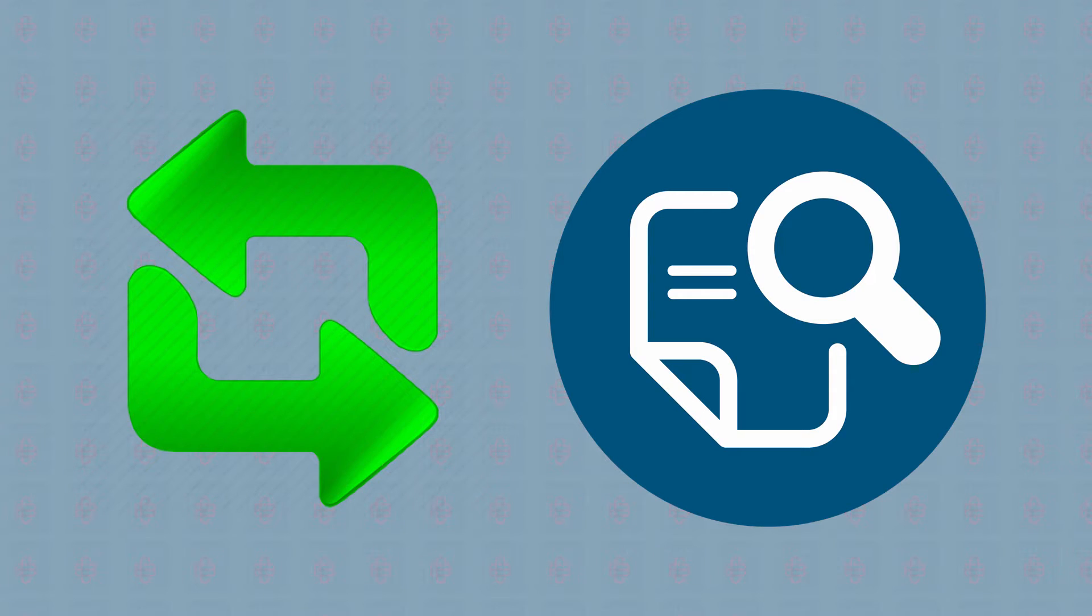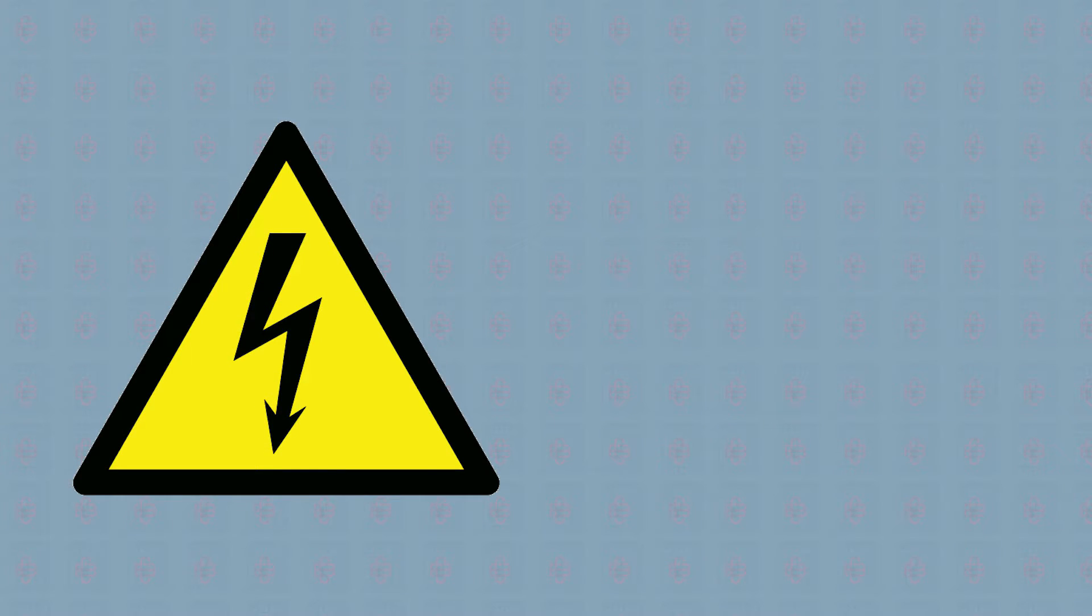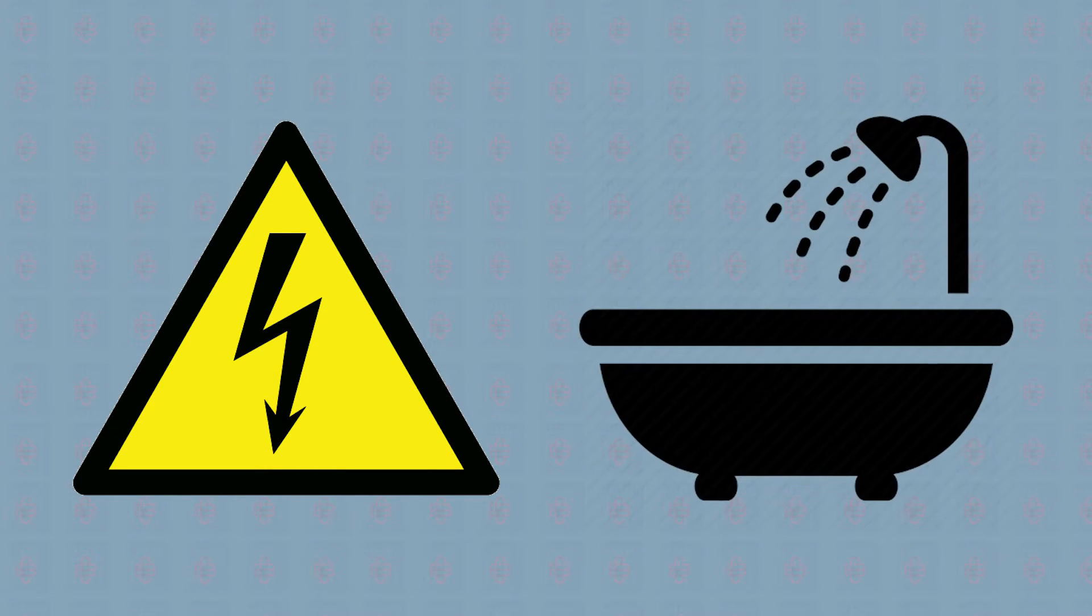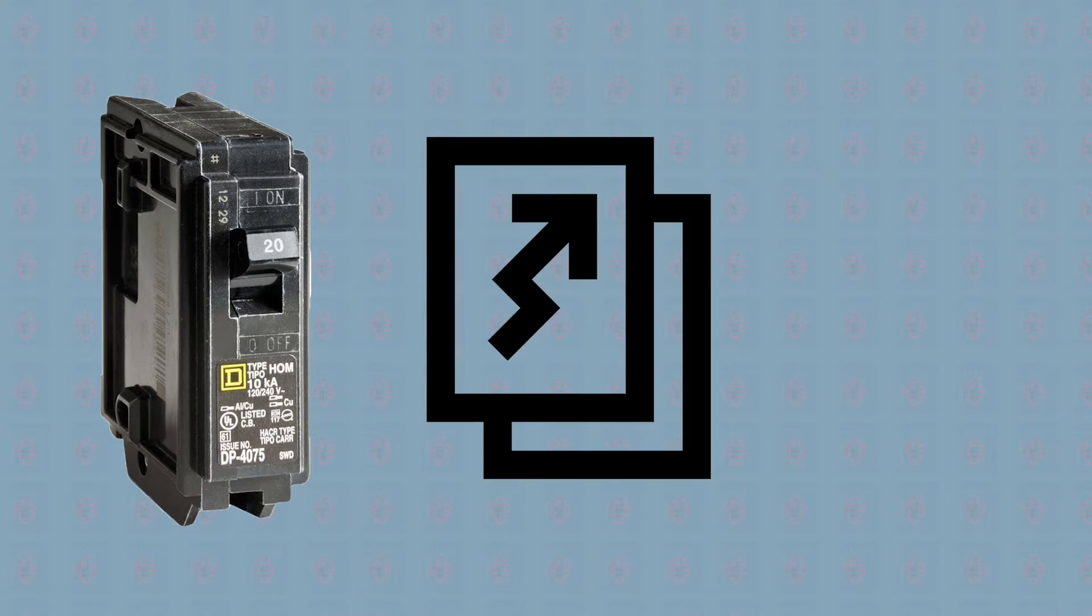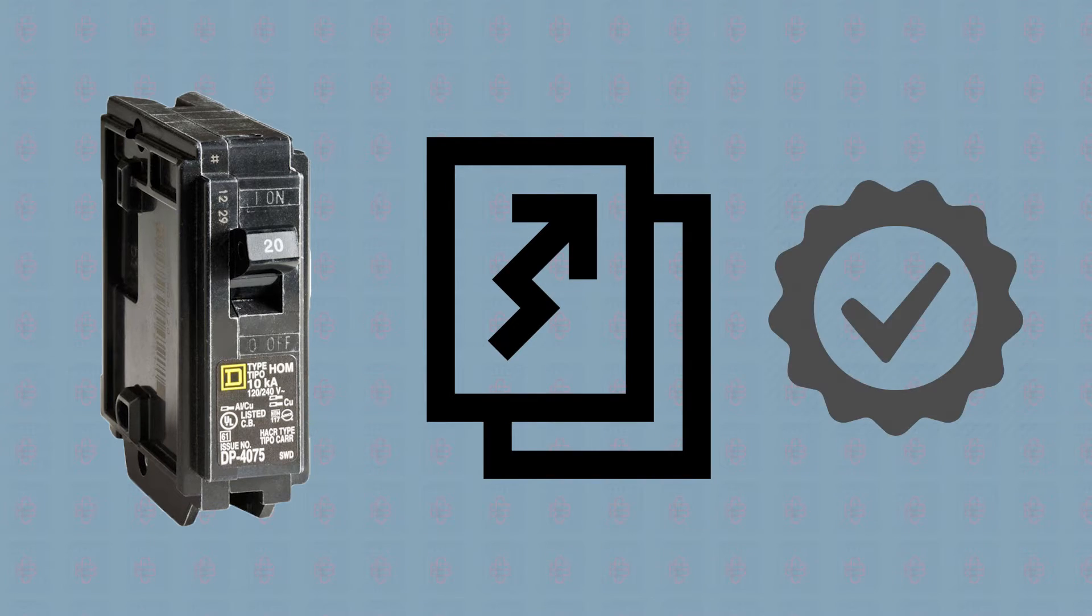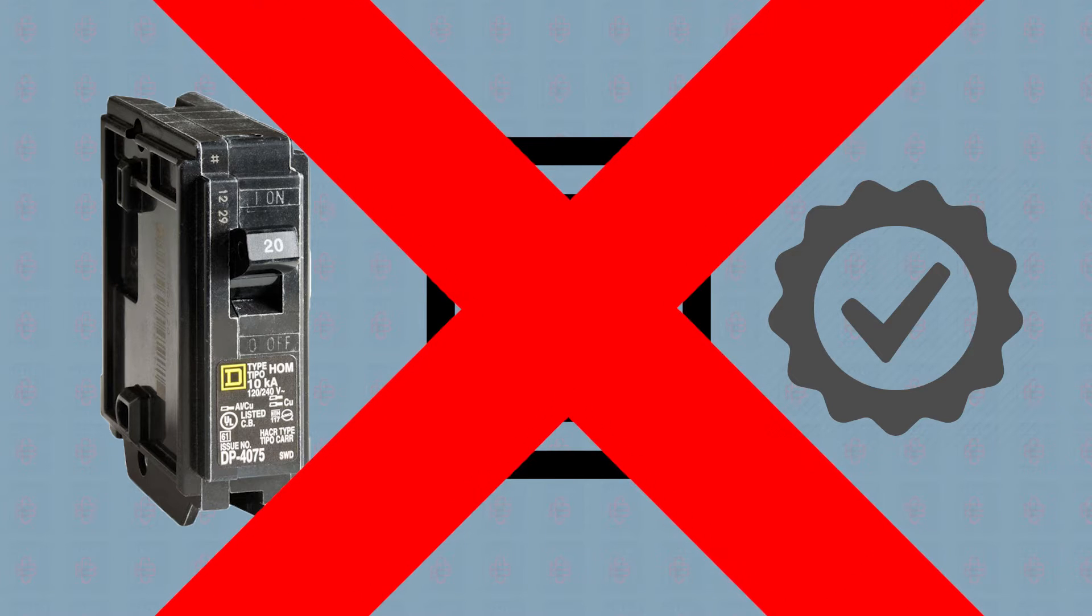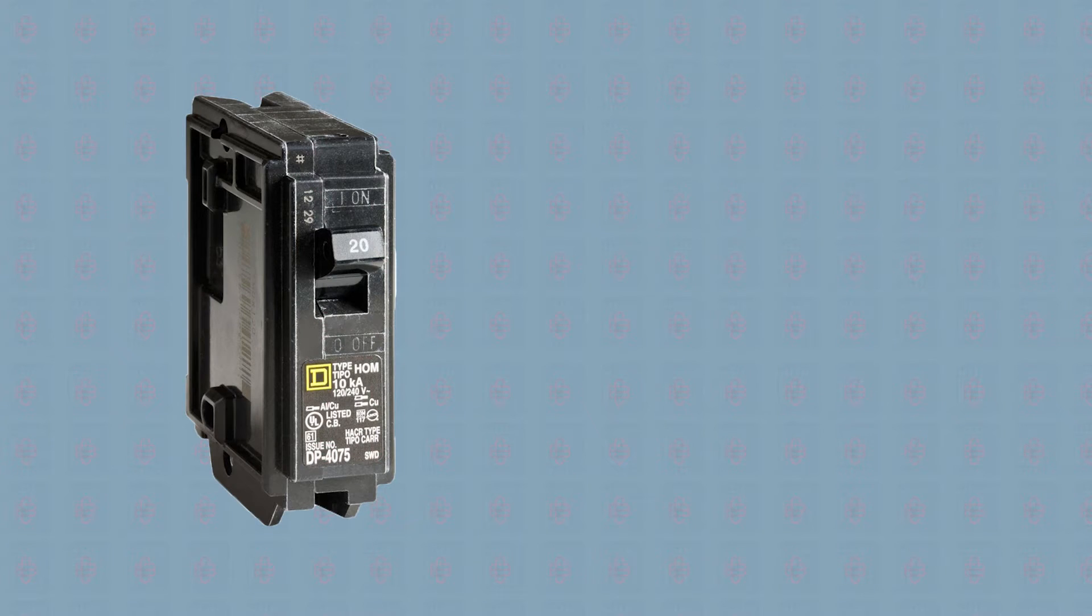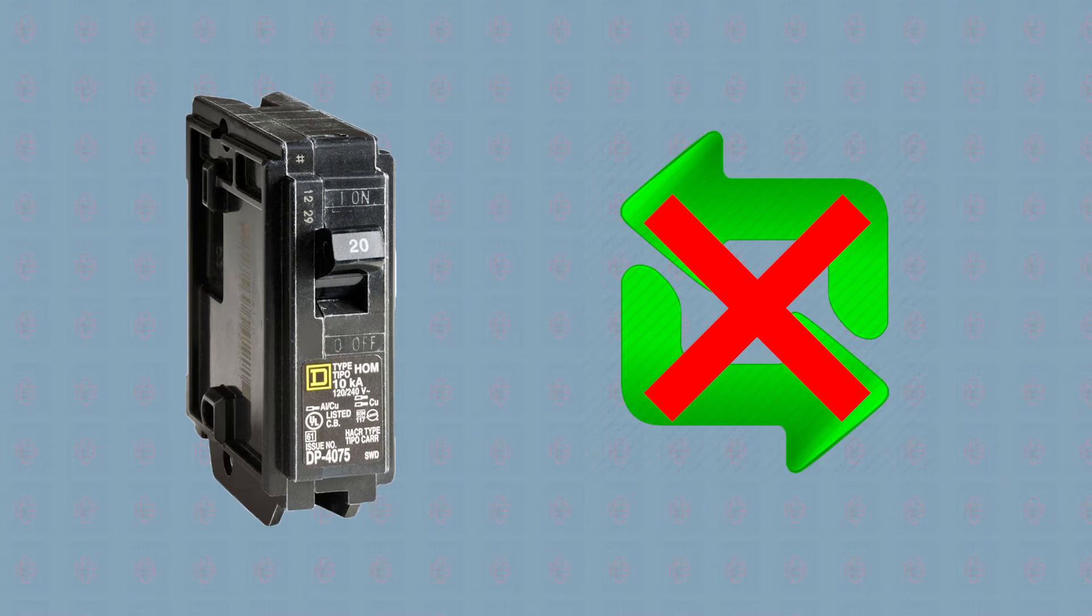You must accommodate for functionality. If you're replacing a high-risk circuit protecting, for example, a bathroom, even if a single pole breaker of the same brand, voltage, and amperage is available, it's not appropriate to interchange because this location requires a GFCI breaker. In other words, some breakers aren't interchangeable because their specs don't line up.